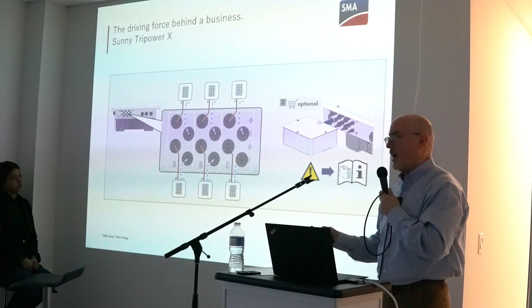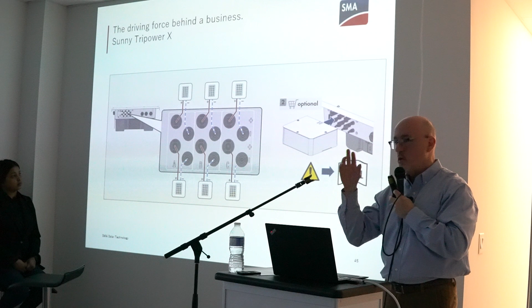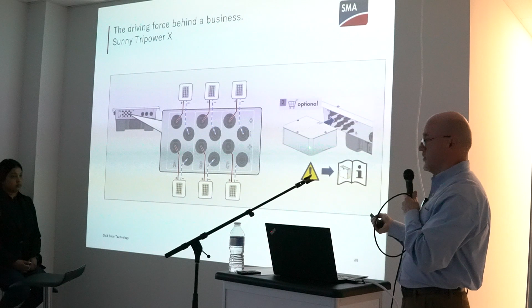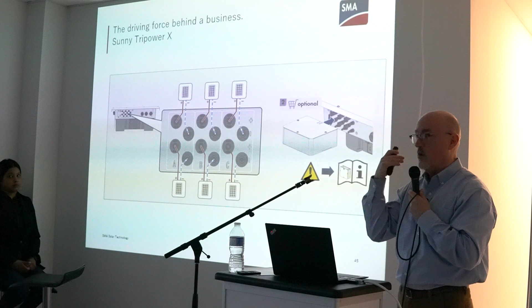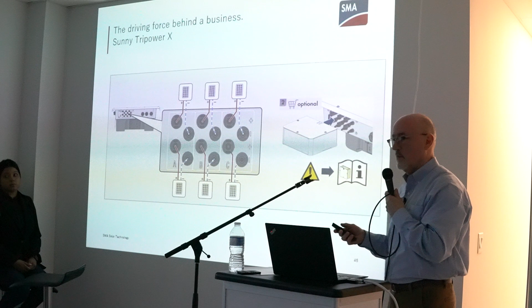There's the DC bulkhead, 6 strings, as I mentioned. One of the knockoffs that we've gotten on the CORE1 is your DC conductors come right into the bulkhead and they're exposed. And so a lot of installers have wanted a shroud around the bulkhead. Now, on the CORE1, we do not offer a shroud option for that. From an environmental standpoint, weather and any of that sort of thing, moisture, no problem at all. But some people don't want those connectors exposed because of different configurations. With this unit, we're going to be offering an optional shroud. Now on the CORE1, just FYI, if you run into a situation where you need that, we do provide CAD drawings for those, but you're on your own to have those produced. But we'll be offering a shroud option on this one.